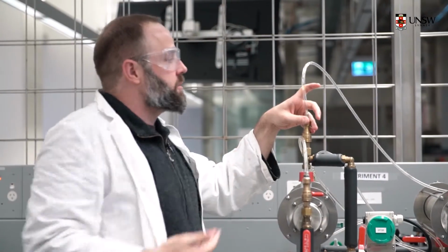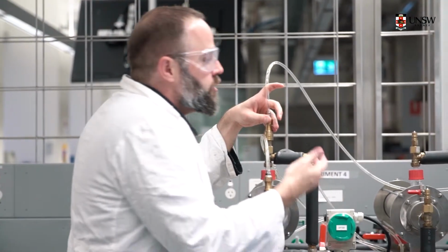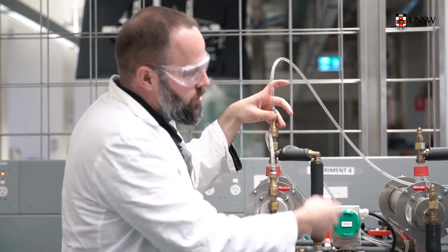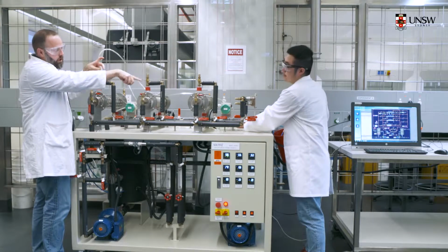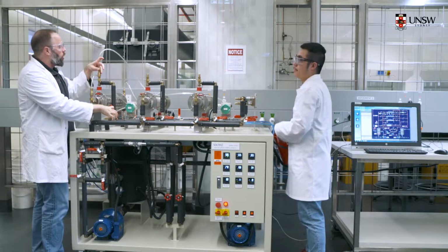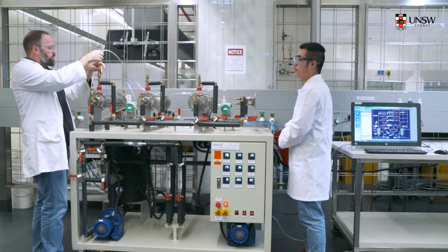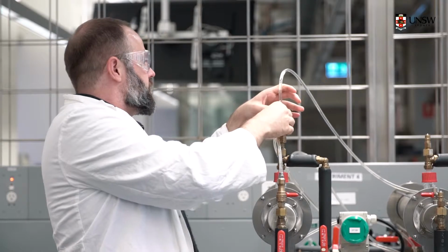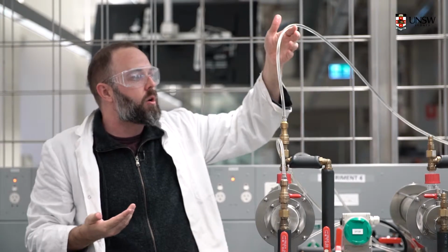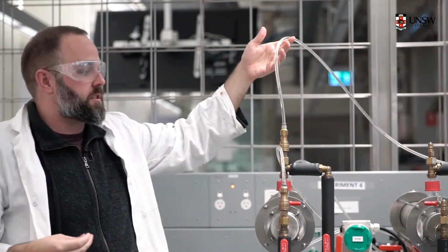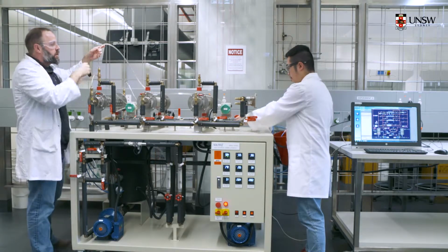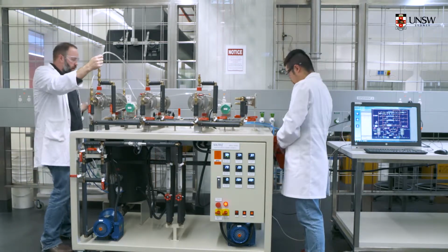All right, so again, there are air bubbles in the line right now. To clear those out, you have to play around with the pressure inside the line. One of the tricks is to open up the area where it's measuring the pressure drop. So if you can go ahead and do that right now. It's open? Yes. Okay, I'll open up my end. It'll start pushing water through. If it looks like there's water leaking, it's not that big of a deal. It'll eventually stop leaking. Now you can see that there are no bubbles in the line at this point. So now you can effectively do an accurate pressure drop measurement. When you're done doing that, close that off so you're not spilling all the water out that way.